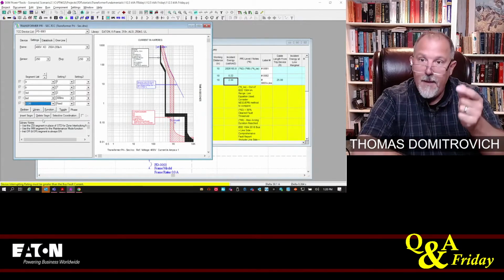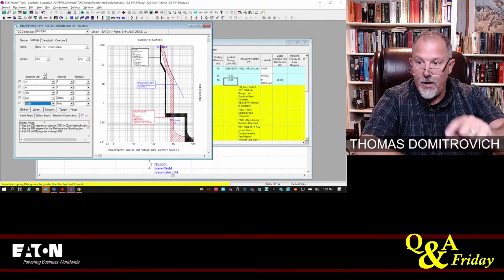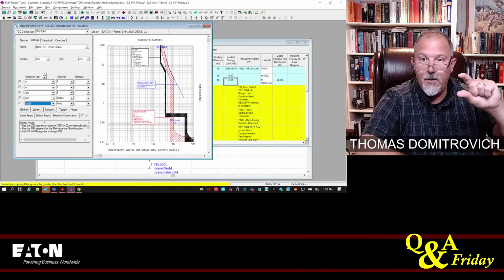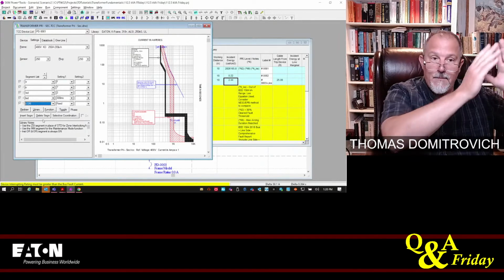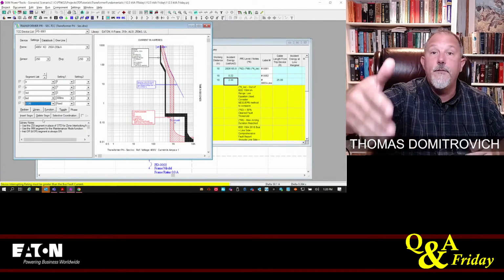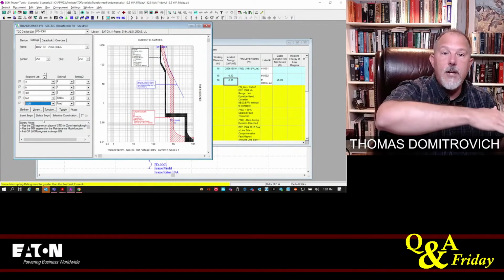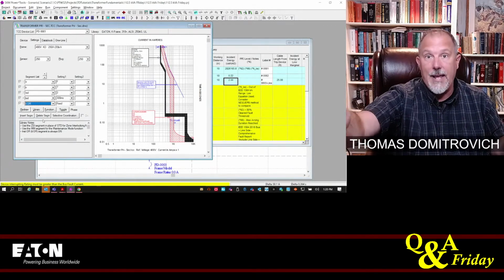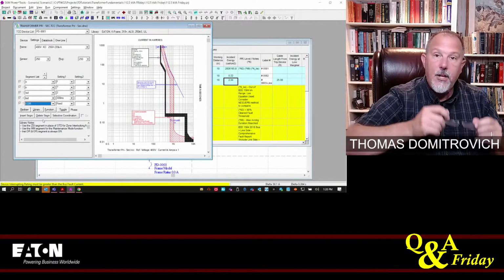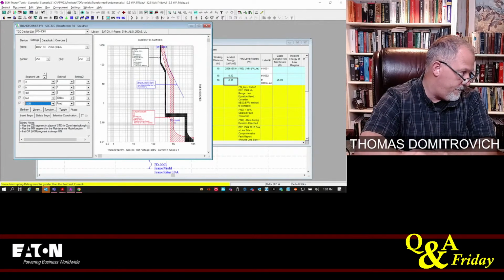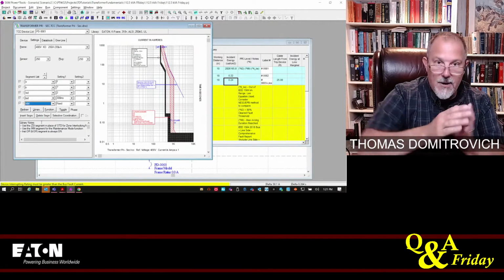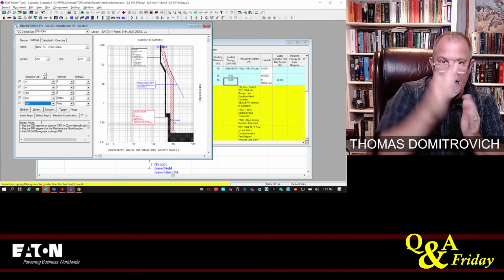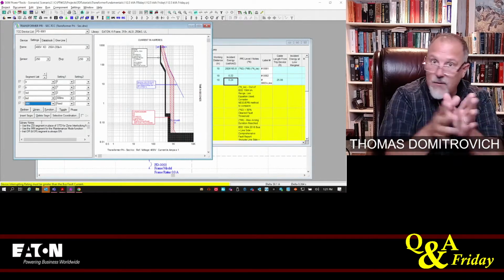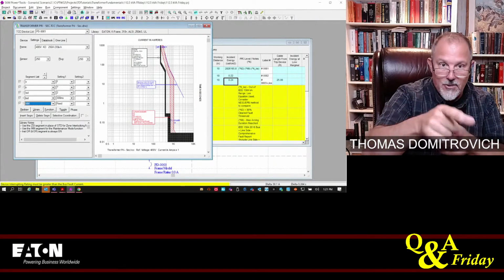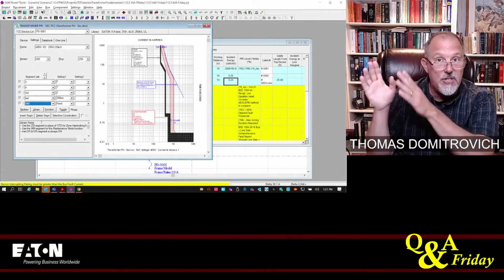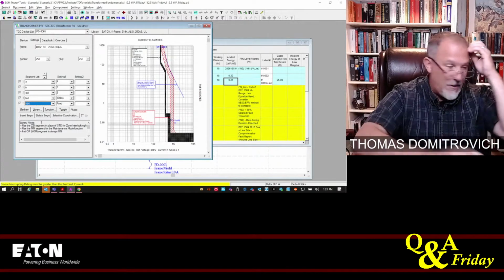When you turn the maintenance mode on the trip unit, right? So you go to that primary breaker. Let's say you're going to work on the transformer, or you're working on the secondary of the transformer at that panel board. You go to the primary and you turn maintenance mode on. And now it took the short time delay and it made it instantaneous. The transformer is energized. I don't have to worry about that energizing current because it's already energized. I'm doing justified energized work downstream.